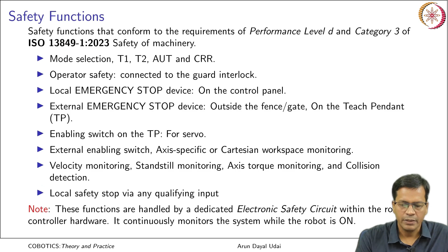Local safety stop via any qualifying input. It can be a failure of any attachment which sends a feedback, and that tends to stop the robot also. These functions are handled by a dedicated electronic safety control circuit within the robot controller hardware. It continuously monitors the system while the robot is on. This hardware is a dedicated one. It is apart from the main controller which executes all the programs, does the forward kinematics, inverse kinematics, everything else. Various function tests are carried out before startup and after recommissioning of such robots.